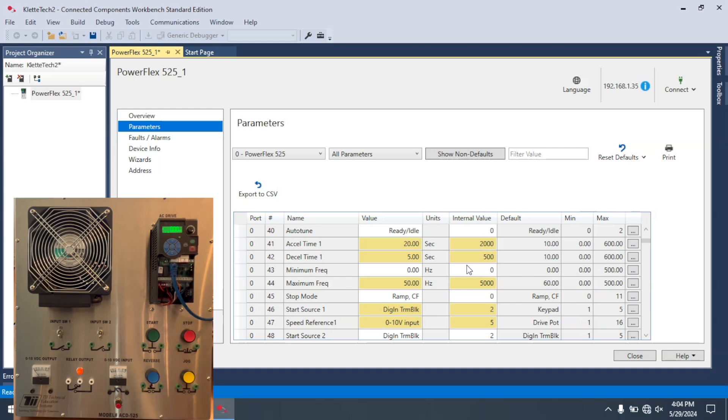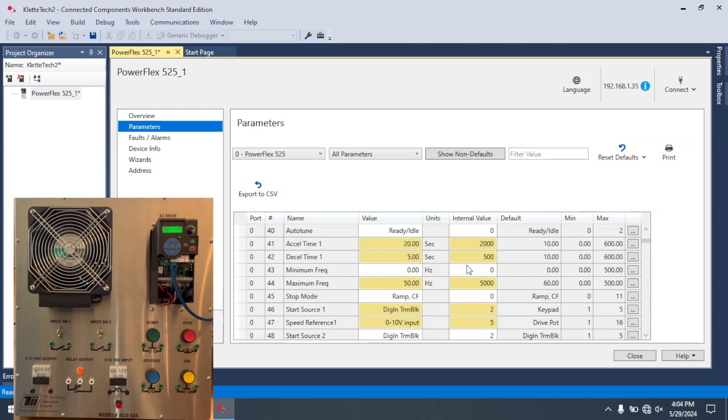The helpful thing about this is let's say I have a VFD that is starting to have some problems. I can go in there before it completely shuts down and pull all the parameters that have been set either manually or through CCW or something else, Studio 5000. I can pull all those parameters out. Then when I replace the 525, all I then have to do is download those same parameters.